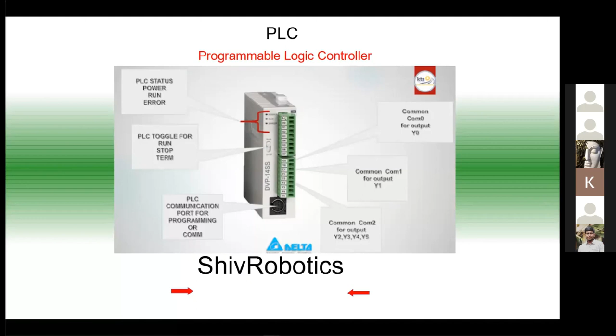And there will always be a toggle switch or push type switch, which is used to run, stop, or terminate a program. And there will be a DIN connector, which is most probably used for PLC communications or to program the PLC from the computer. And there will be screw connectors or WAGO connectors, which will be used for inputs and outputs. Normally, the top portion will take inputs from the external world, and the bottom portion will be used for controlling the outputs. So this is a very general architecture of the PLC.